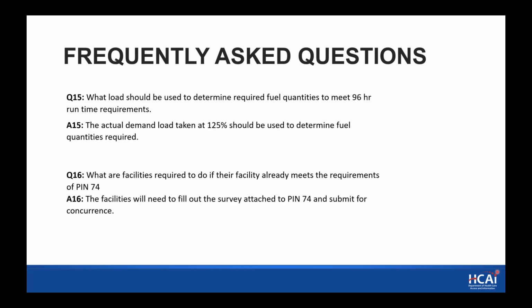Next slide, please. Number 15. What load should be used to determine fuel requirements to meet 96-hour runtime requirements? The answer is the actual demand load taken at 125% should be used to determine fuel quantities required. So if you have an existing facility and you are transferring load to this potentially new source or an existing source, you could take the demand load metered, multiply that by 1.25, and then use that to determine the fuel required to operate for the 96 hours.